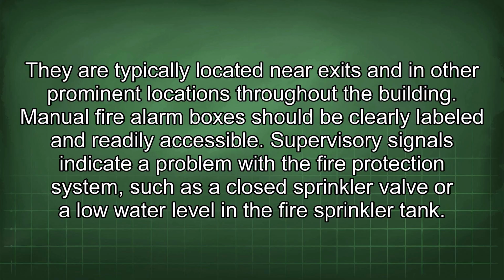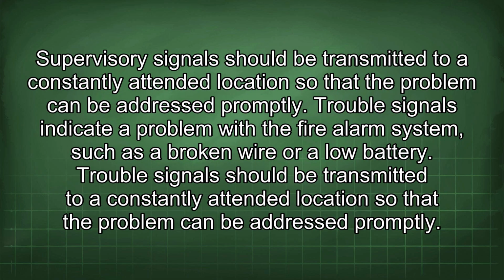Supervisory signals indicate a problem with the fire protection system, such as a closed sprinkler valve or a low water level in the fire sprinkler tank. Supervisory signals should be transmitted to a constantly attended location so that the problem can be addressed promptly. Trouble signals indicate a problem with the fire alarm system, such as a broken wire or a low battery. Trouble signals should be transmitted to a constantly attended location so that the problem can be addressed promptly.